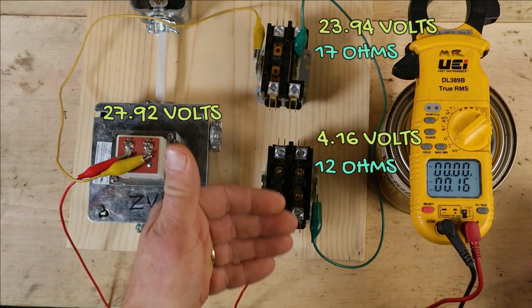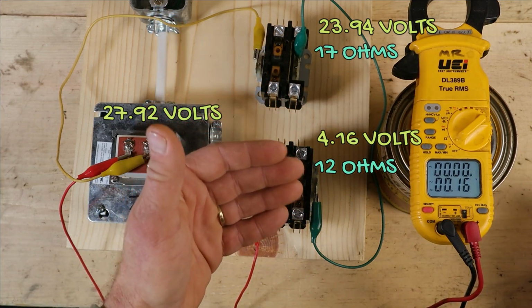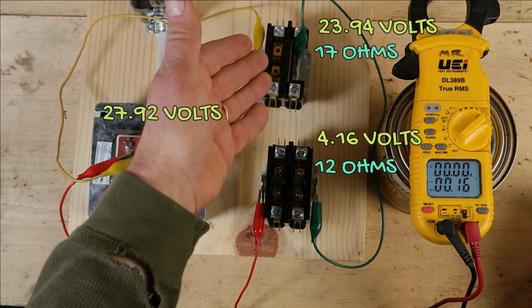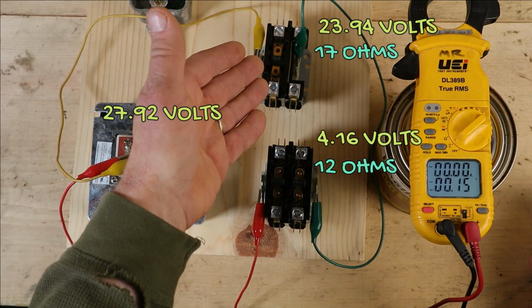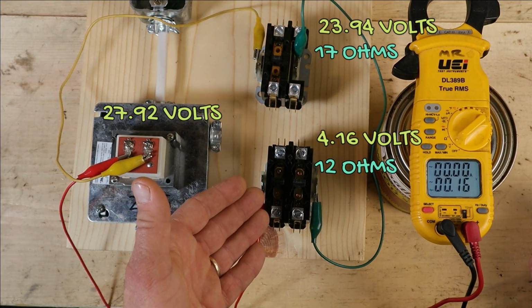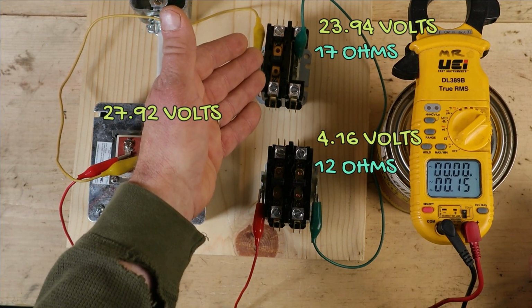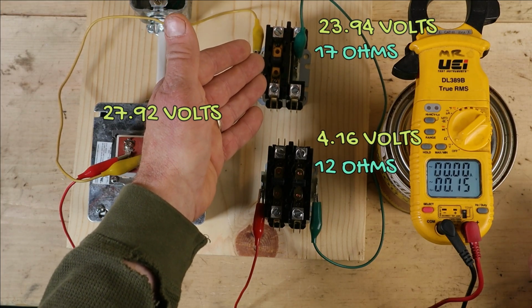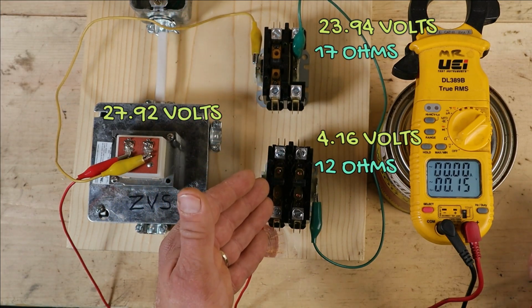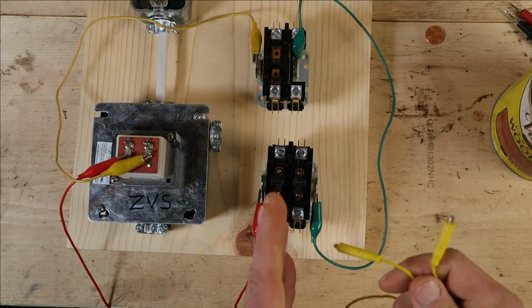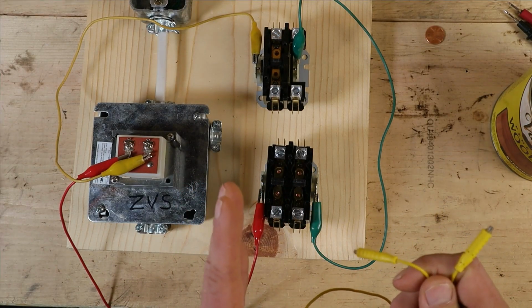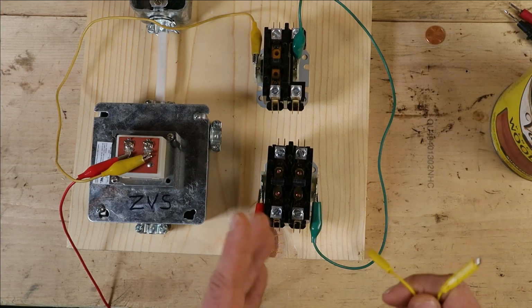So the different resistance values caused the voltage to split proportionally. The higher resistance got more voltage, the lower resistance got less voltage, and because this one got more voltage, it had just enough to pull the contactor closed, where this one at 4 volts did not. Now I'm going to show you something interesting, and please don't do this when you're trying to diagnose a system, and I'll explain why in a minute.